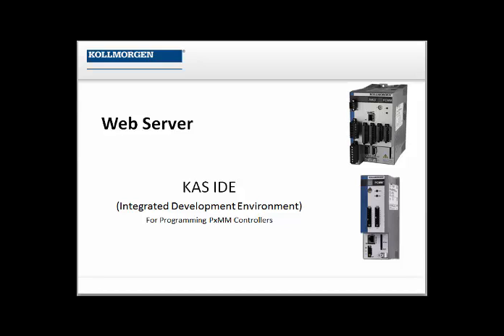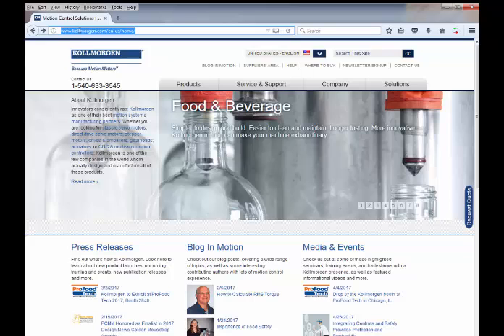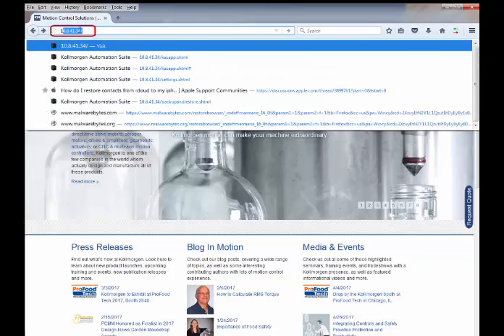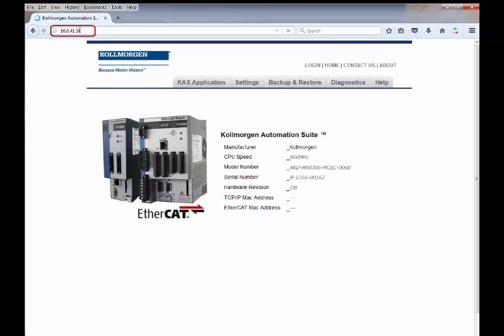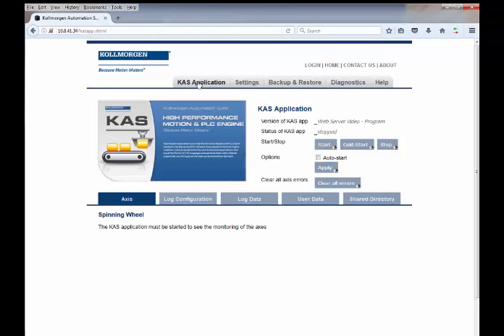The KAS web server is accessible independent of the IDE directly from a web browser or inside the IDE. Firefox will be used to demonstrate from a web browser. Typing in the PDMM's IP address from the entry screen opens the web server. The web server is password protected. Without entering the password, many settings can be observed but not changed. The default password is administrator, which can be changed by the user.